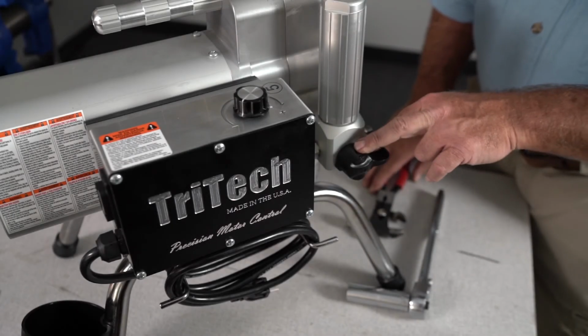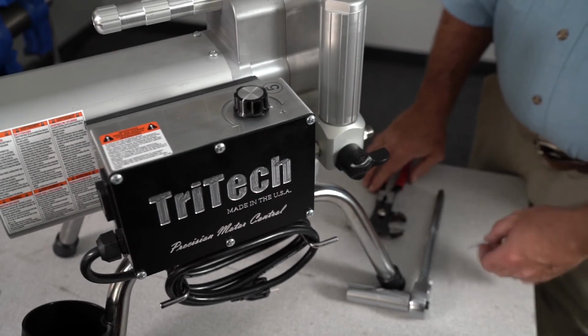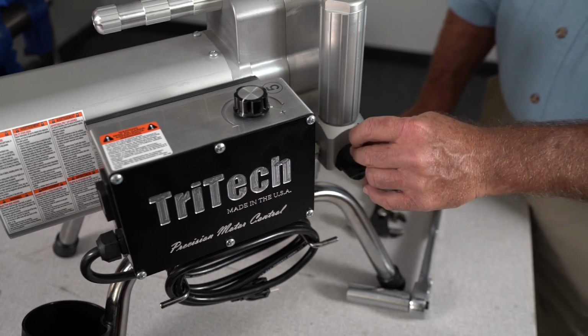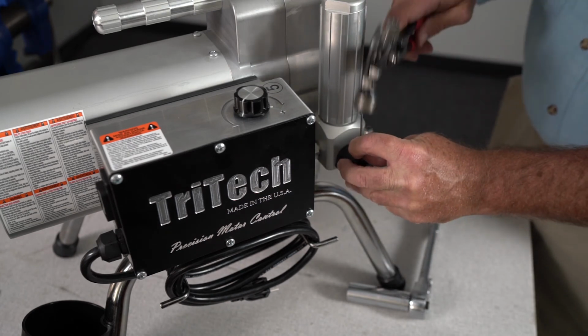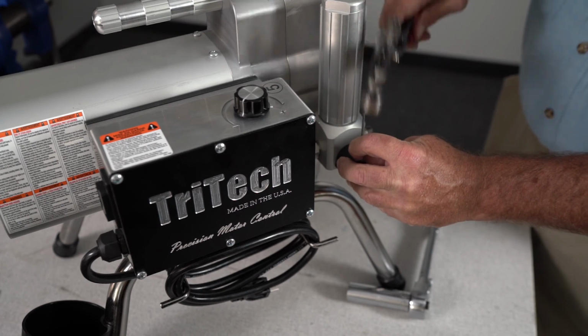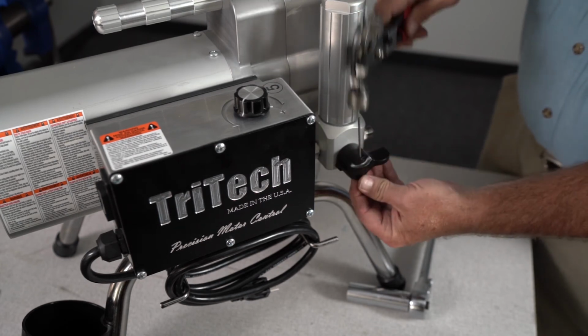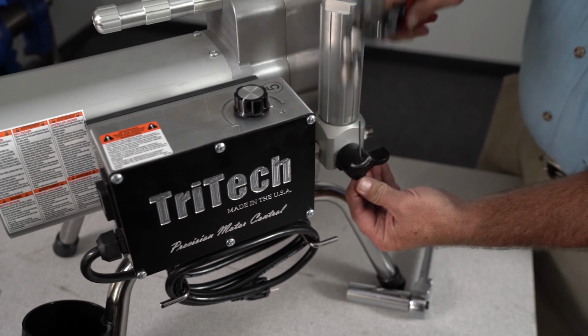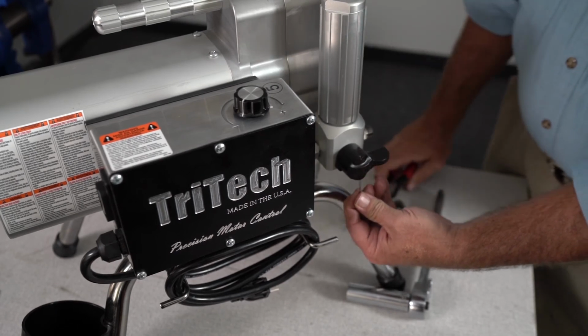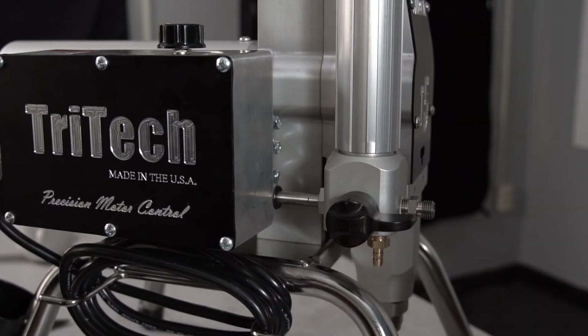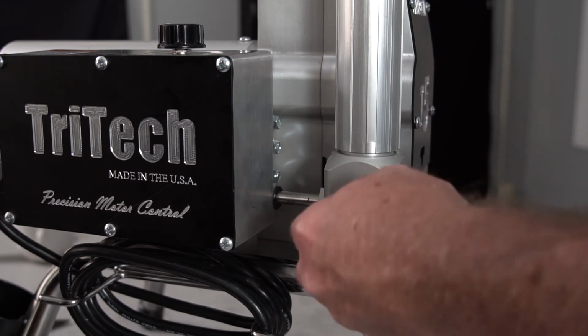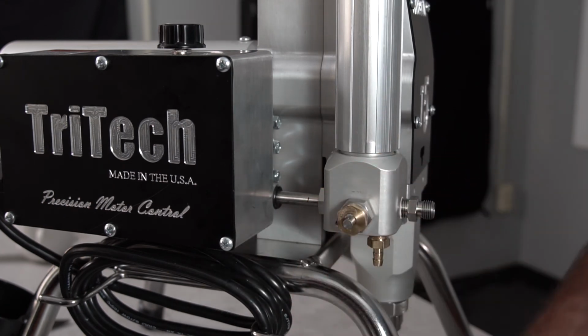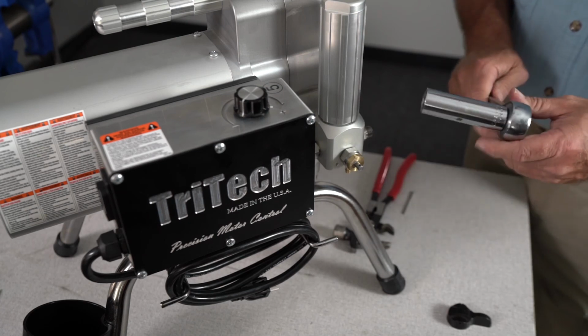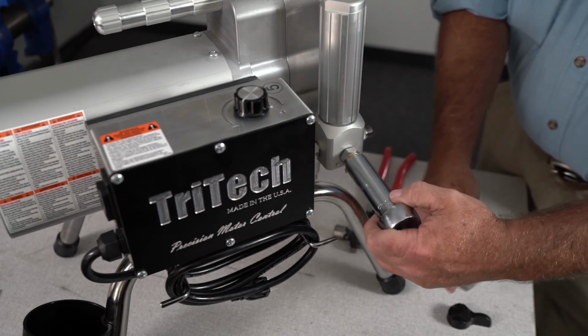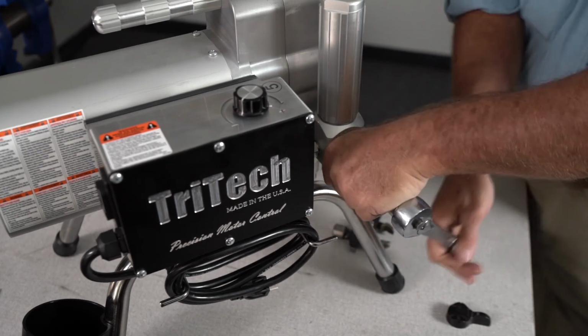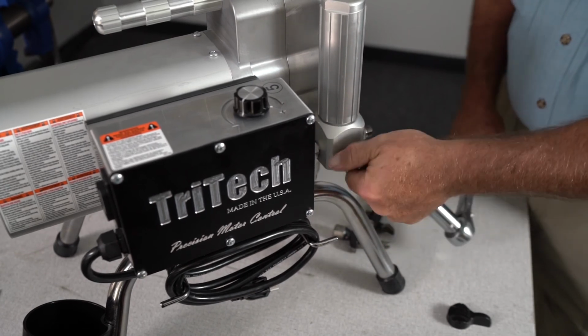Okay, now we're going to remove our bypass valve. So the first thing we need to do is knock out the pin. You just use a punch, or you can use the same pin. You push that through, pin comes out, and you remove the handle and the cam. And then you can use a 3/4 socket and unthread the valve from the housing.